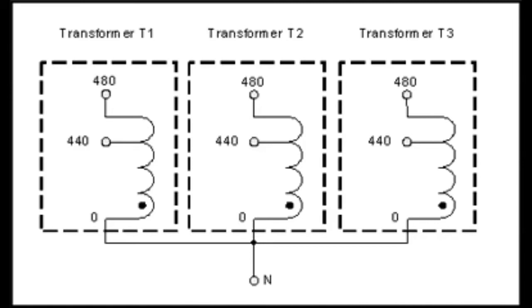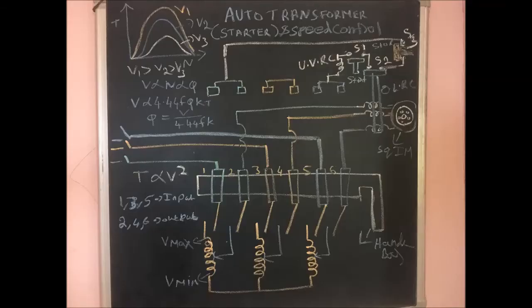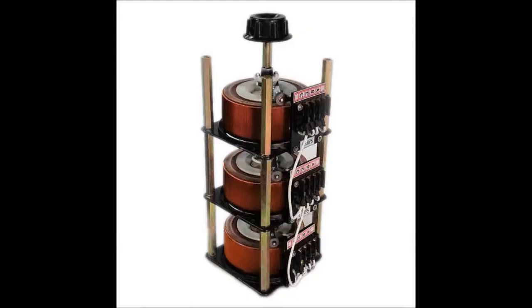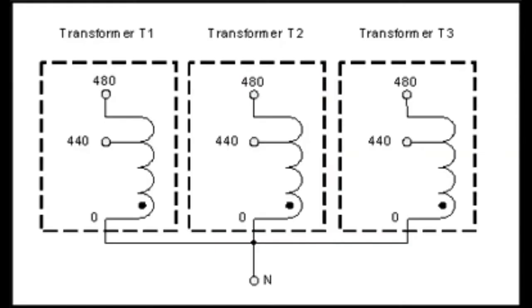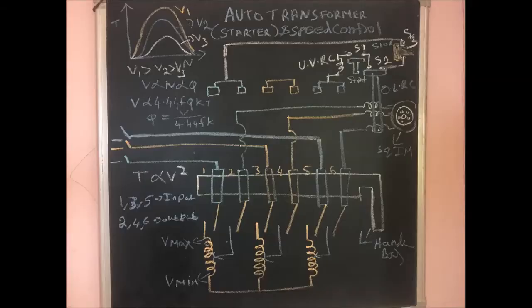Listen how it is working. Now you are moving the handlebar upward. At that time, the under voltage release coil gets magnetized and it attracts the handlebar. At the same time, switches 1, 2, 3, 4, 5, 6 are closed. Now depending upon the number of turns at 2, 4, 6 the voltage goes. So the minimum voltage is 200 volts or 300 volts. According to the motor rating, we will set the initial conditions. Therefore, the motor runs normally. Suppose the voltage is less than the standard value, the under voltage release coil magnetic power goes very low. At that time the handlebar moves down, switches 1, 2, 3, 4 open, and the motor is safe.